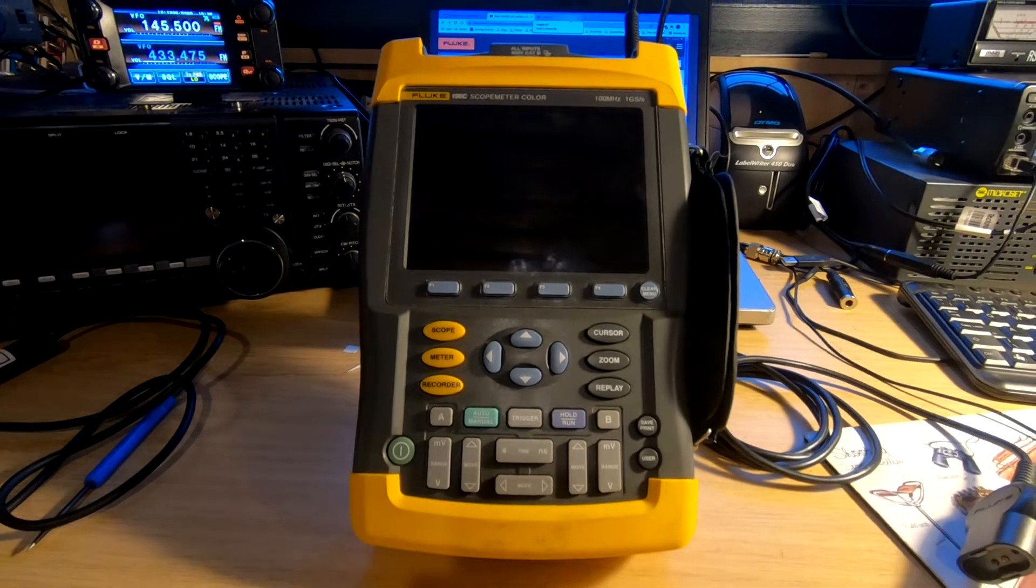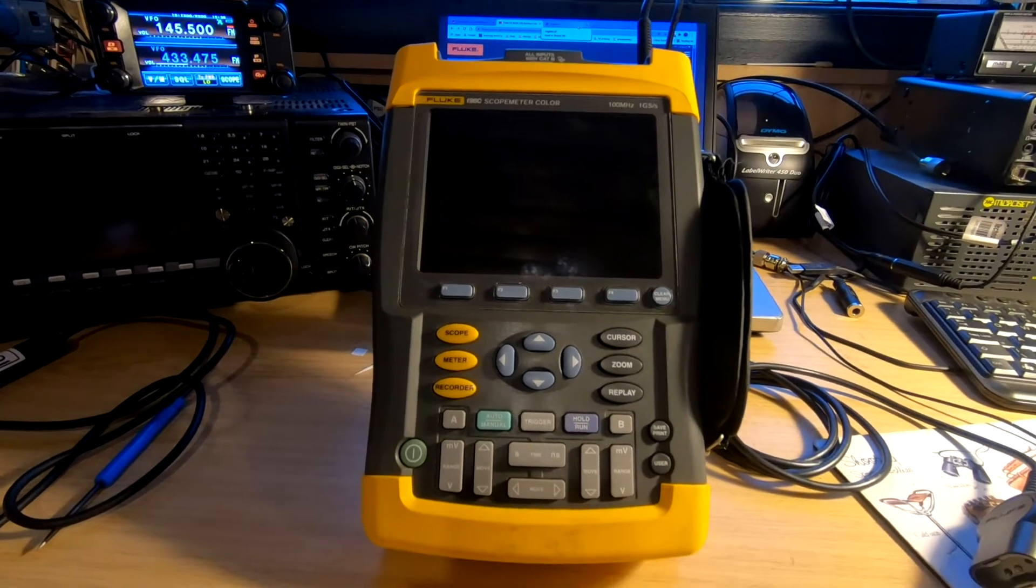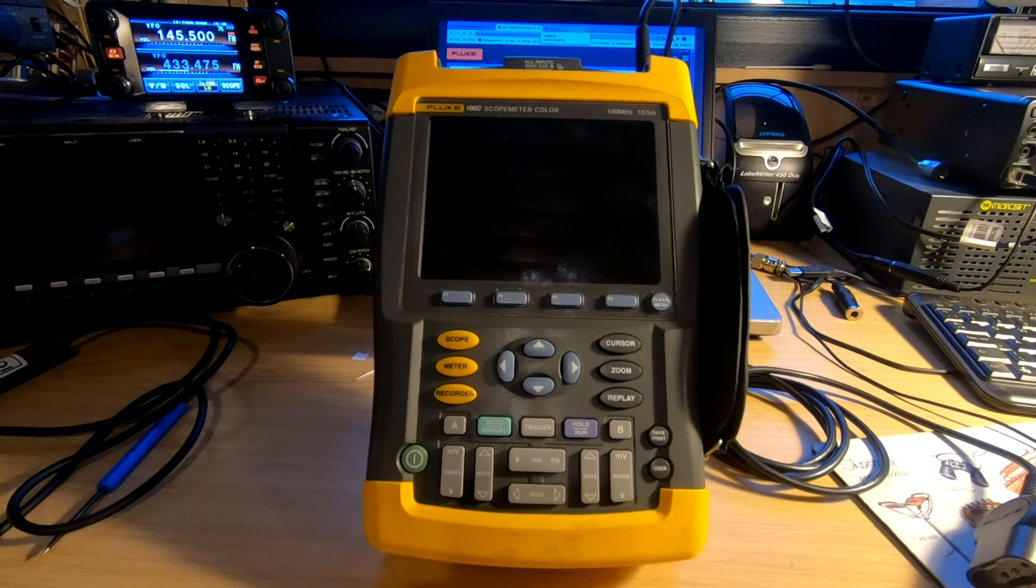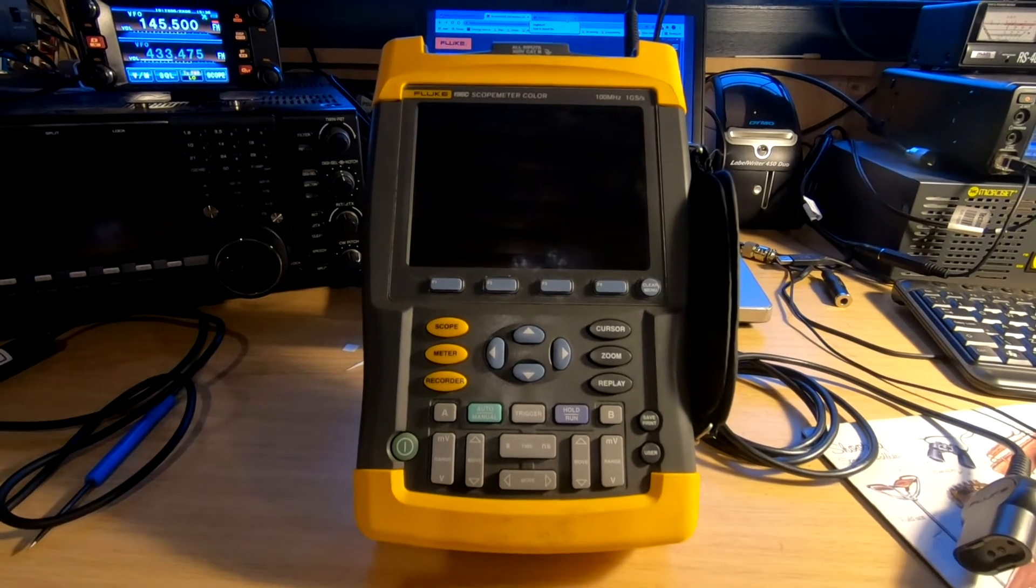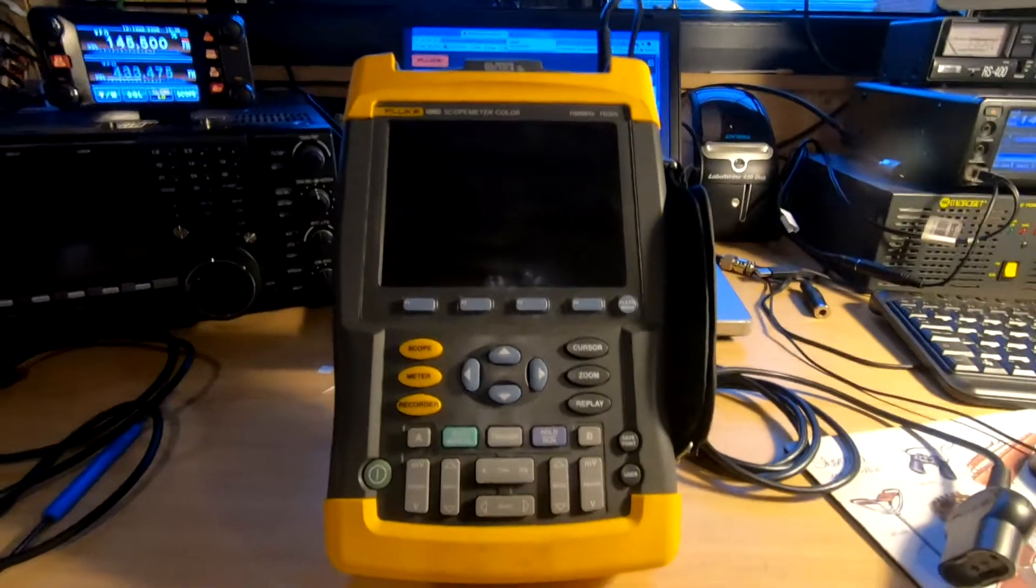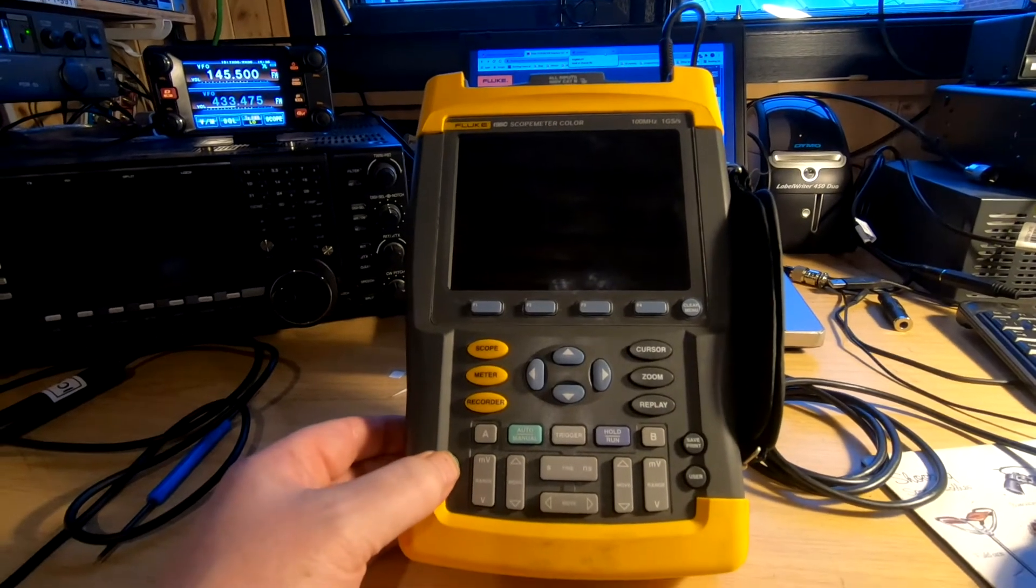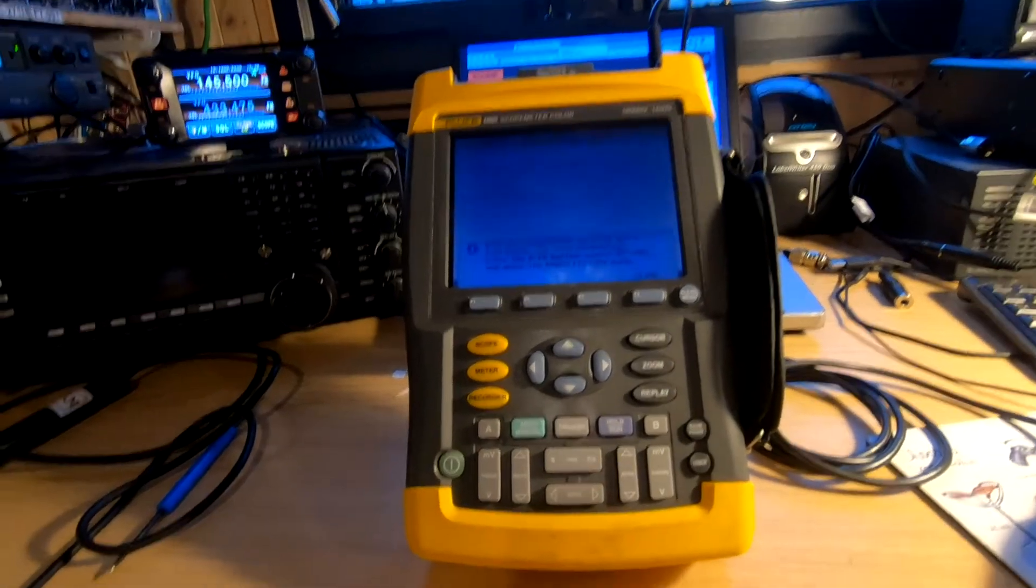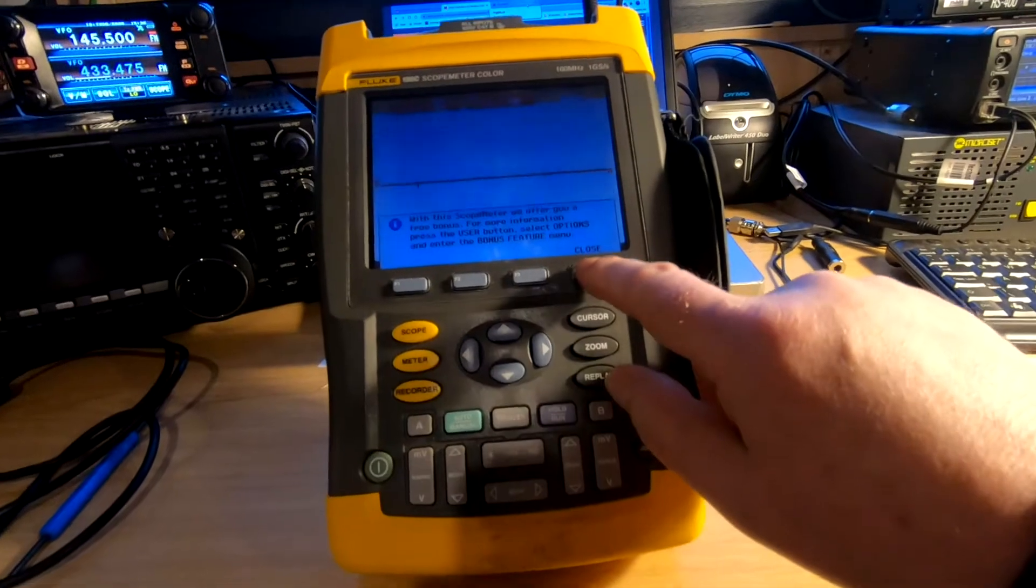This video shows how to do the firmware update on a Fluke 196C ScopeMeter. It's currently running version 7.05, but we'll check on that. We'll do a quick power up and get into the next screen.